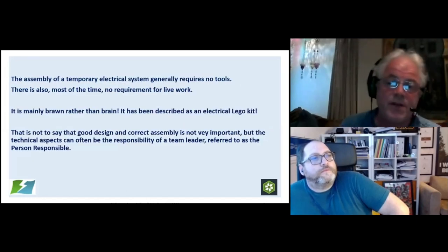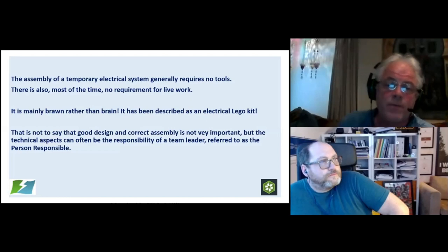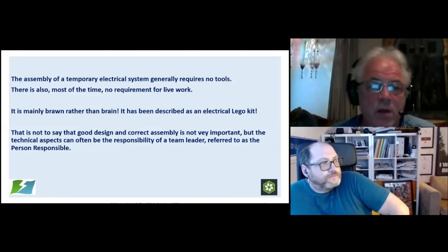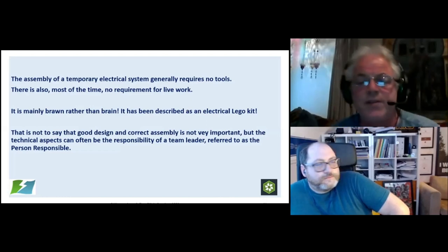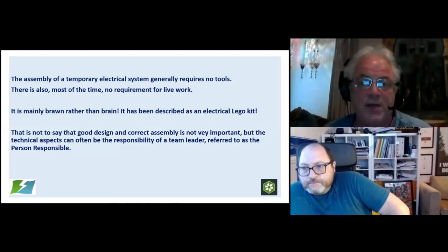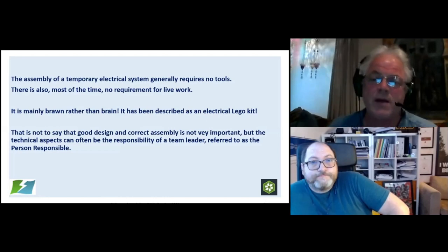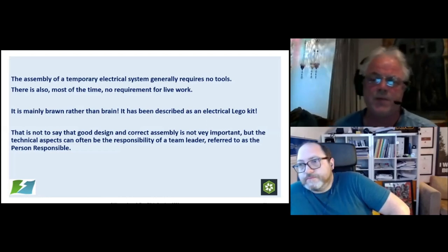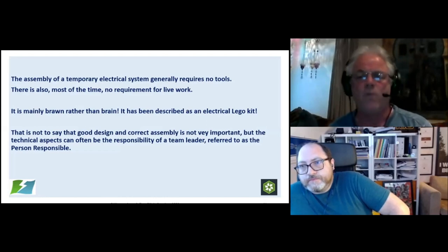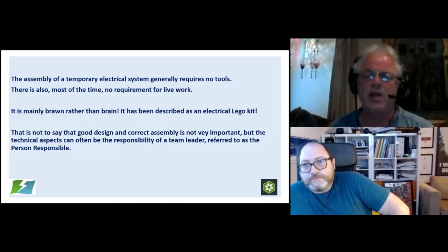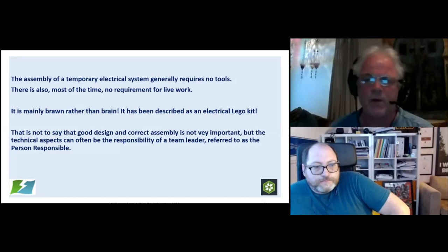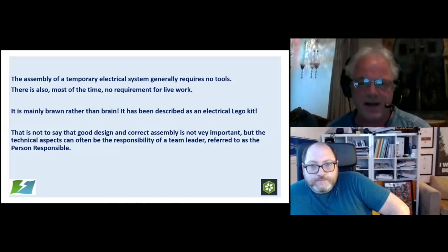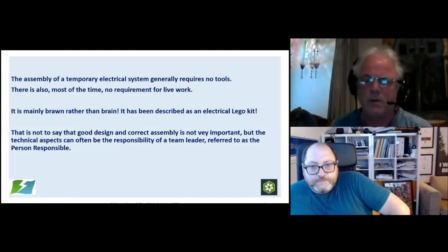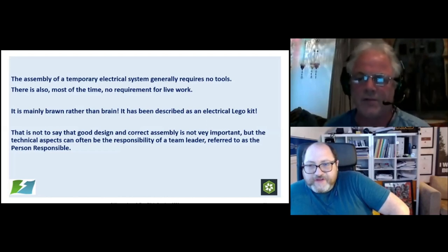Generally, it doesn't require any tools. Most of the time, there's no requirement for any live work. We do occasionally find systems that are connected onto bus bars. Obviously, if we are connecting directly onto a bus bar, then we will need to arrange for shutting down, isolation, and all the rest of it, permit to work systems and whatever. So that's a fairly lengthy, fairly drawn out process. It's not something where you can just connect on there, wear some rubber gloves and hope for the best.